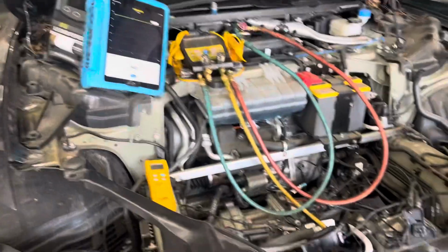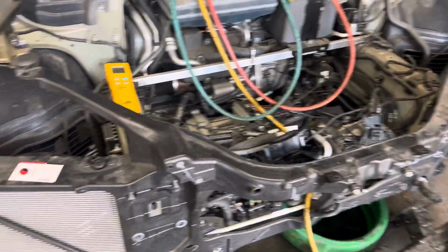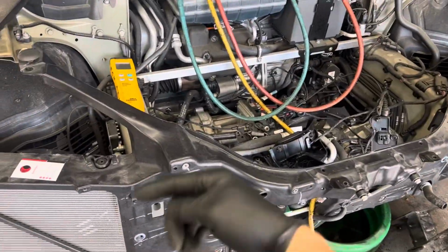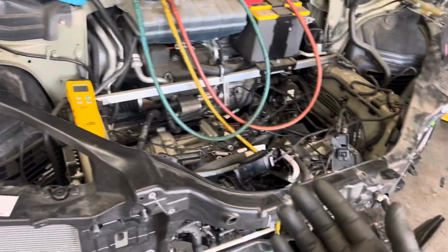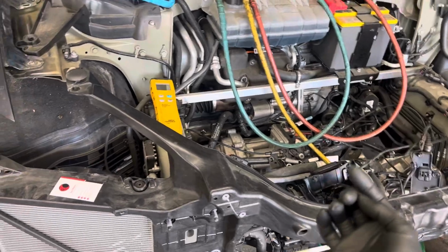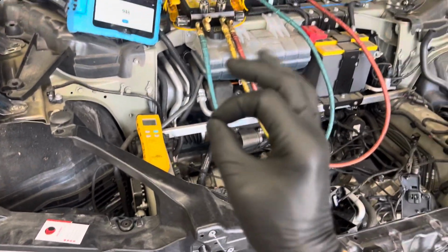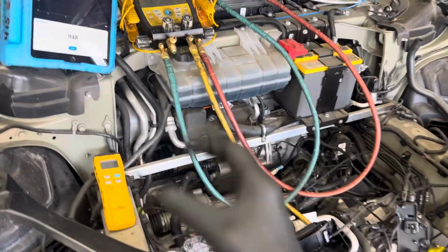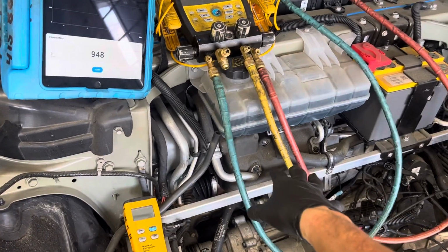It's under a deep vacuum. So what does a technician normally do? They need to remove the things. You would normally just take off the bolts, open it up, and the humidity right now is about 80%. So that humidity would get sucked into the system that has just freshly been recovered, and it's cold. The motor is cold and it has a few ounces of oil in it.